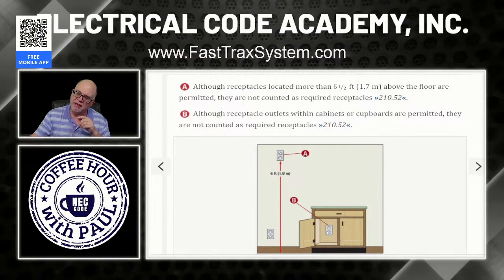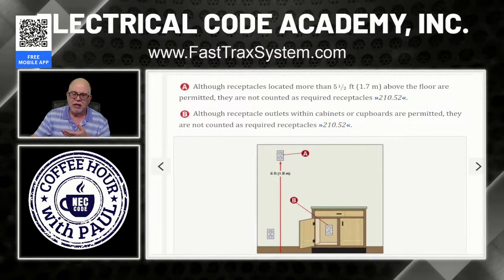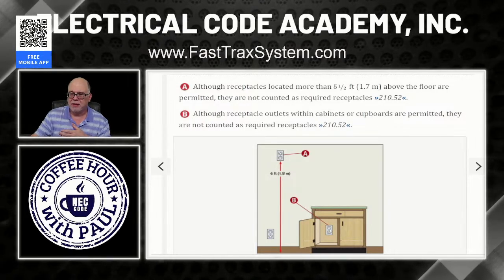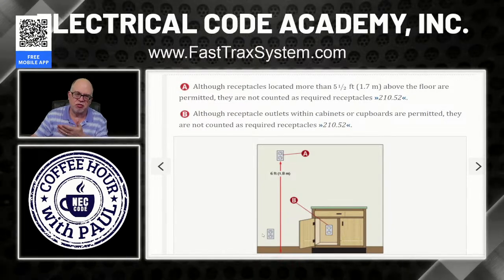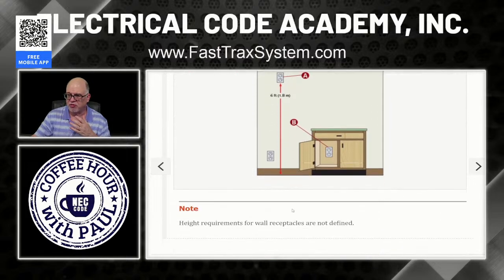B, notice this one's inside of a cabinet. If this was the 6 foot, 12 foot spacing, and then it ended up being behind a cabinet, then the carpenter or the cabinet folks come in and cut it in back here, and your inspector comes in and fails you. Why? Because these inside of a cabinet or a cupboard do not count the same as these out here that are for the spacing. Okay? You can have one in there, but it's additional. It's extra. It doesn't meet the spacing requirement. So that's what we're talking about with B. Although receptacle outlets within a cabinet or cupboards are permitted, they are not to count for the required receptacles in 210.52. They're just there. If you want to have extra ones, that's fine.